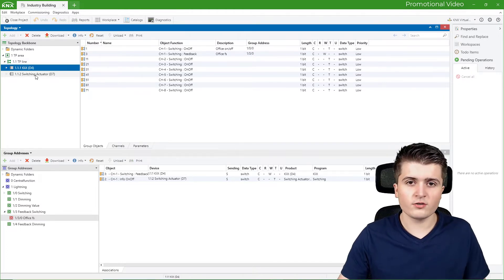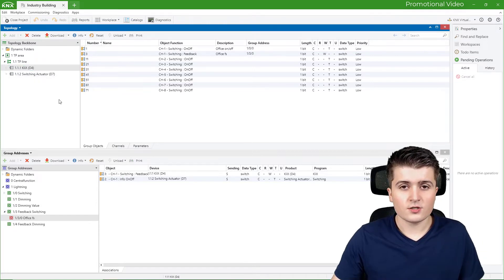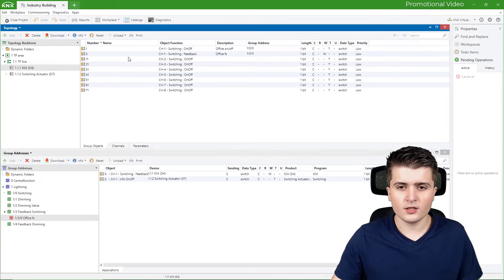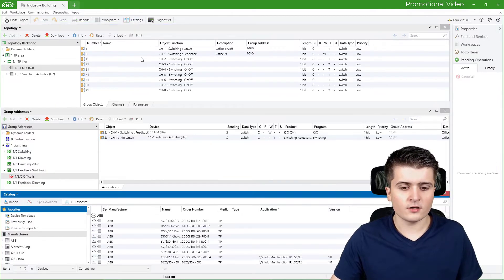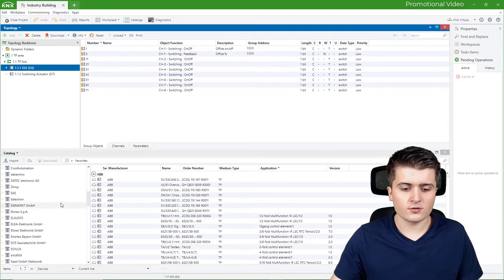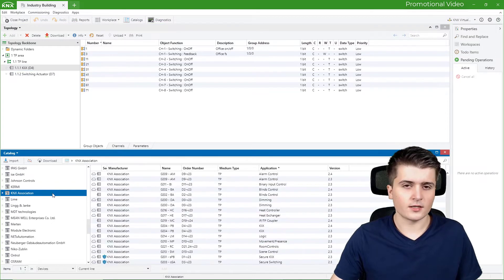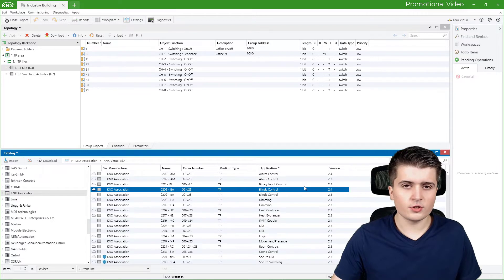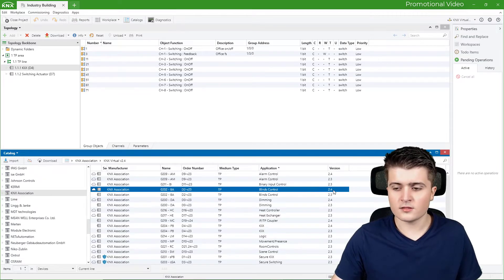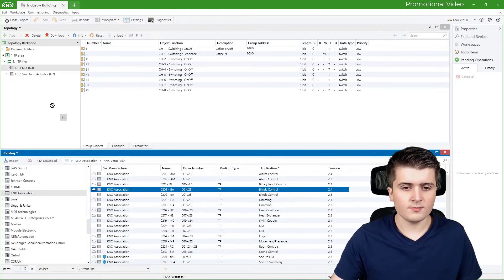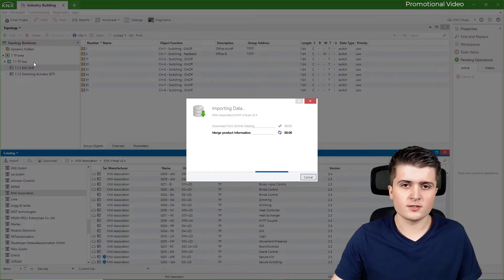Our project currently doesn't have a blind actuator, so let's add one. To add the blind actuator simulated by KNX Virtual, I open up the catalogs page and scroll down to KNX Virtual, also listed under KNX Association. There we need 'Blinds Control' — I'm using version 2.4, though you might have a newer version. I simply drag and drop it onto my twisted pair line.